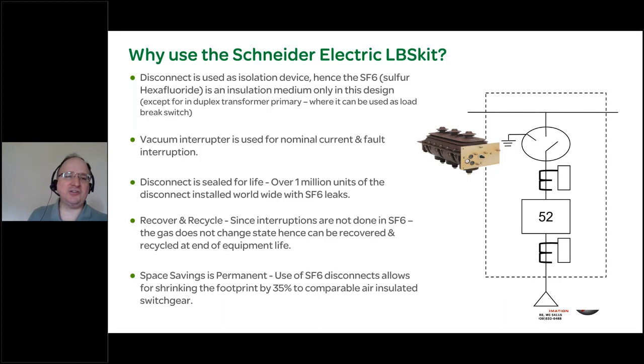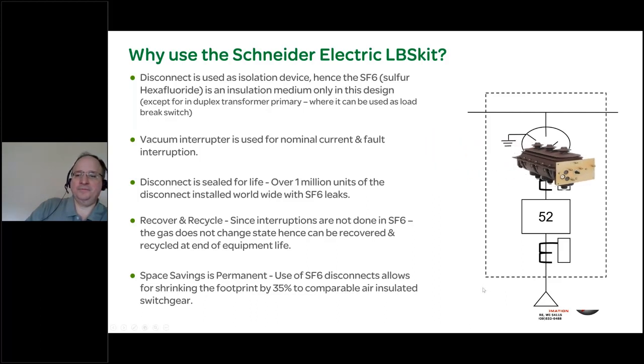It is an SF6 switch. It is a very low pressure switch, approximately 6 PSI. There's over 1 million units of these installed in the world. This is a very mature product. It's been around since the 1990s. And there's never been a single leak just because the pressure is so low inside. And the switch is available again in 5, 15, and 27 and 34.5 kV flavors.